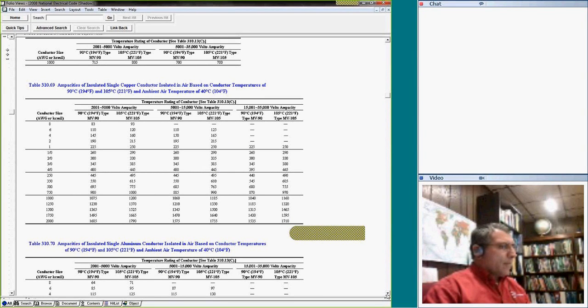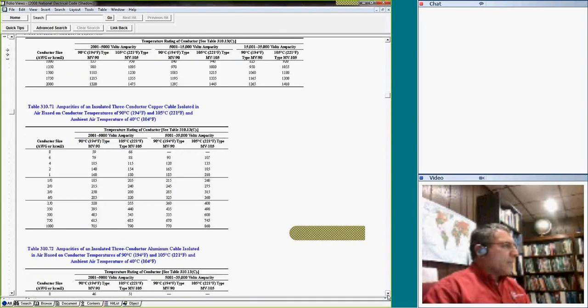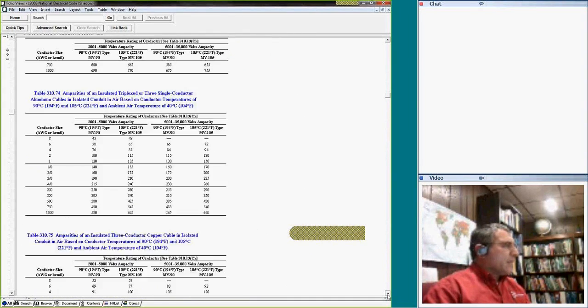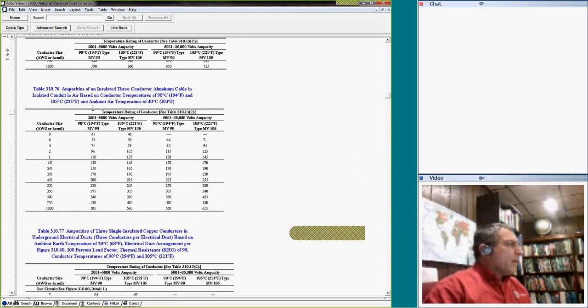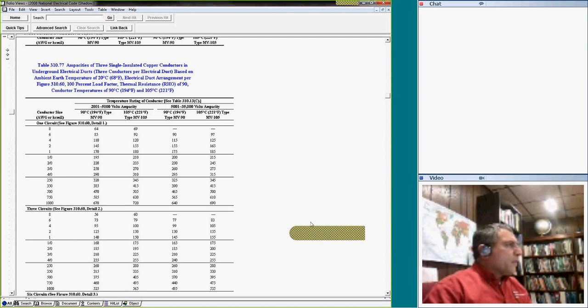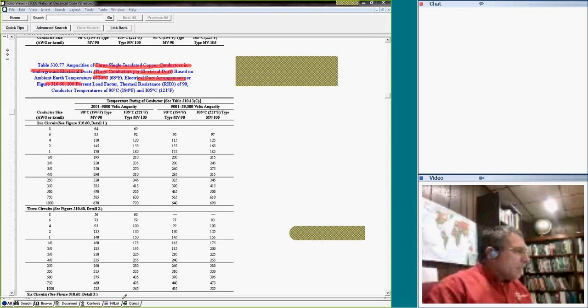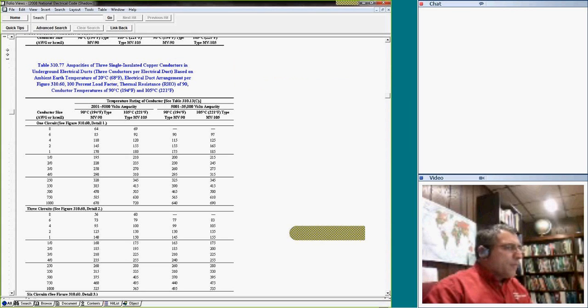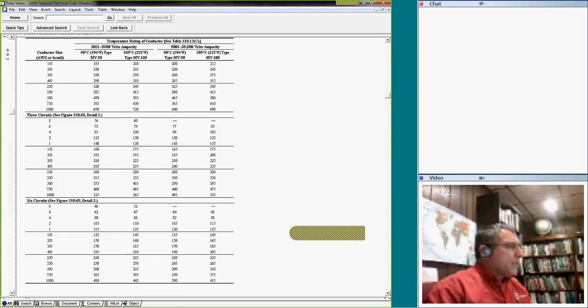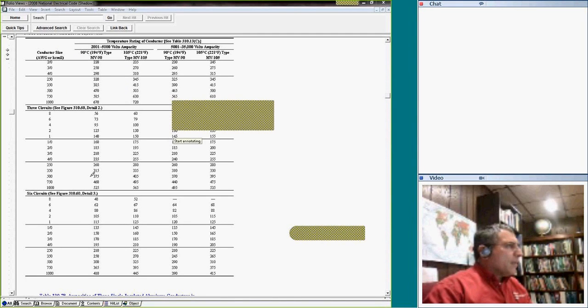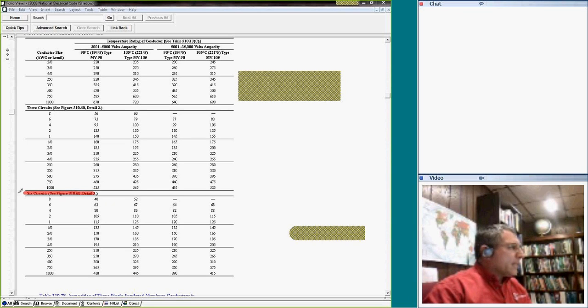Let's look at some of the NEC and so forth, which is one that makes a little bit of sense. Base configuration. Okay, I need to do one in the underground. Here you go. So for this one, ampacity of 3 single conductors in an underground duct, 3 conductors per duct, based on an earth of this amount, the duct arrangement as I've shown it. And this is for the medium voltage. Let me see if I should go one more. This is the configuration I showed you guys, except for medium voltage cable. Here, and this is detail. Remember detail 3, guys, 6 ducts.